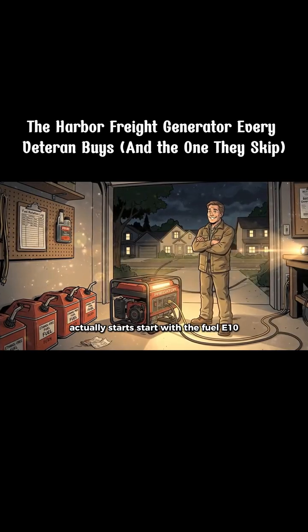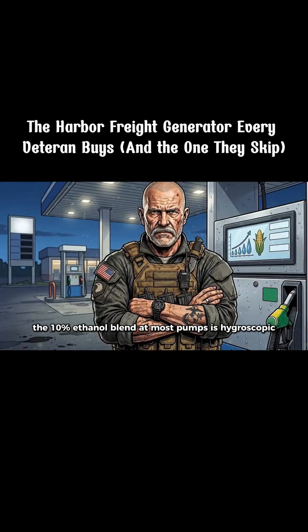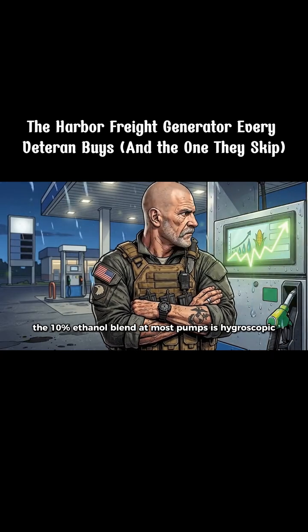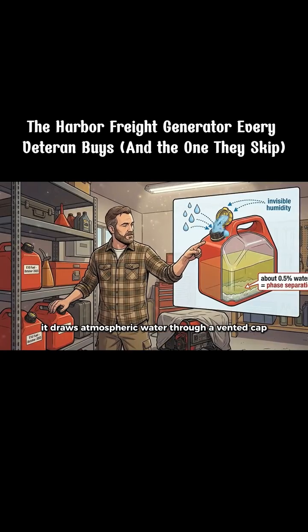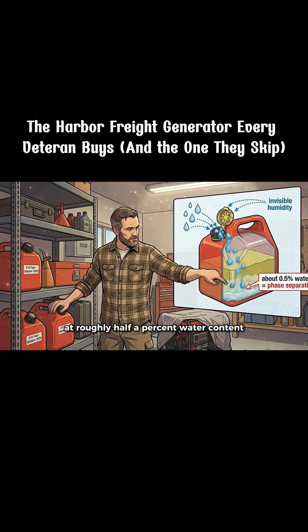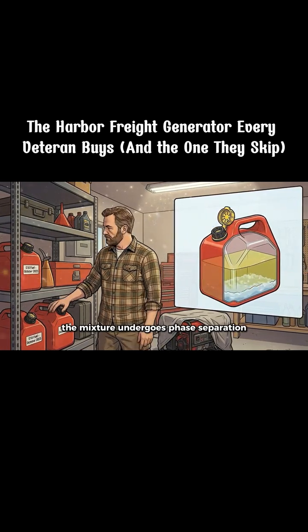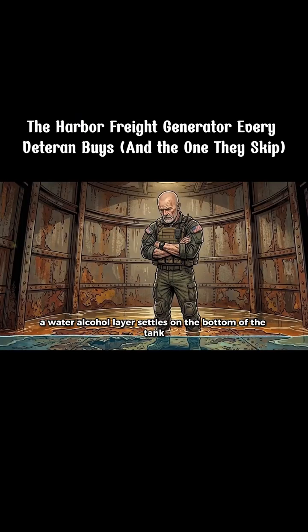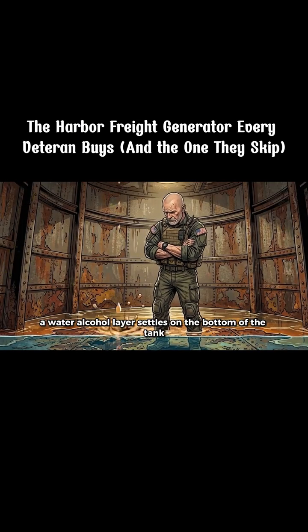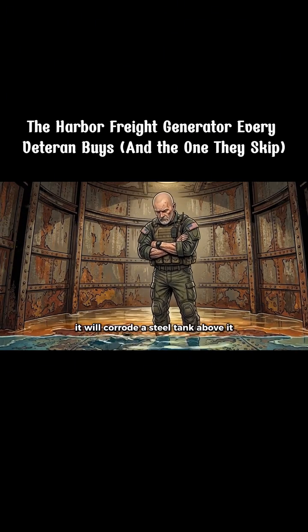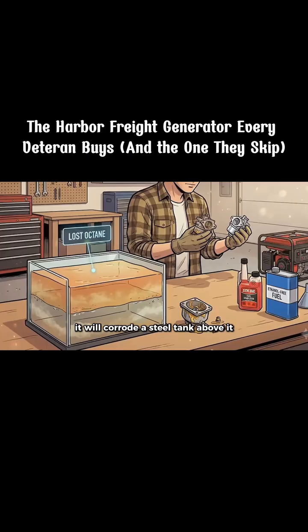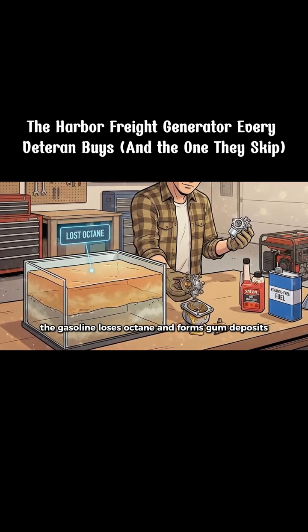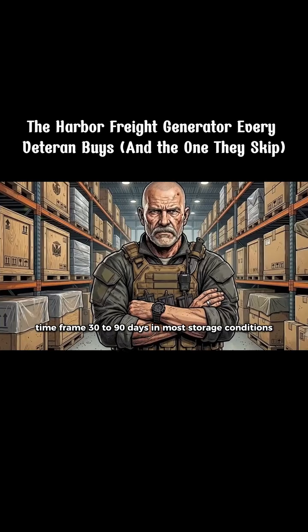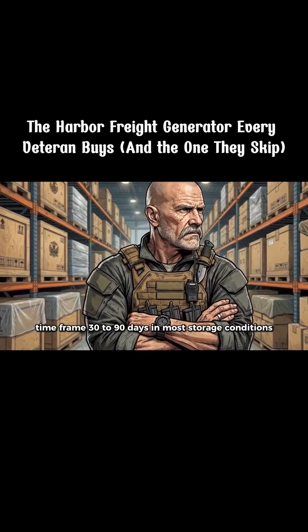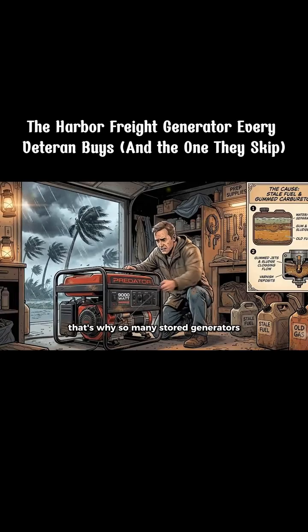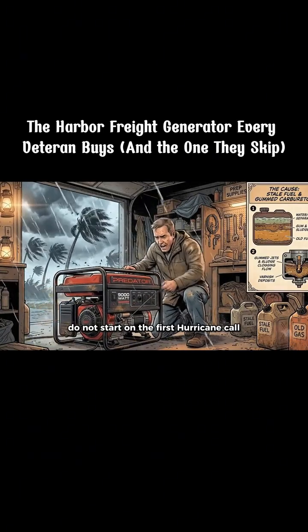Start with the fuel. E10, the 10% ethanol blend at most pumps, is hygroscopic. It draws atmospheric water through a vented cap. At roughly 0.5% water content, the mixture undergoes phase separation. A water alcohol layer settles on the bottom of the tank. That layer will not combust. It will corrode a steel tank. Above it, the gasoline loses octane and forms gum deposits. Time frame, 30 to 90 days in most storage conditions. That's why so many stored generators do not start on the first hurricane call.